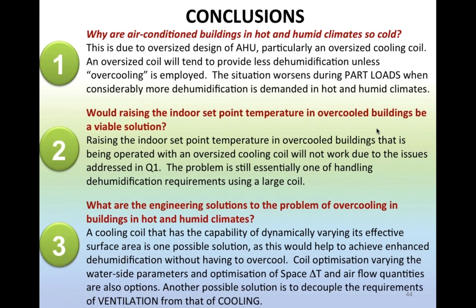It's very difficult. I am talking about a conventional vapor compression-based system. If you're going to achieve your latent load through some other means, like a desiccant system, it's a different computation. I didn't do that. I'm just taking the case that you've got chilled water supply temperature coming at 6 degrees. I think I used 6 degrees in my simulation, and I'm trying to ensure that we stay on that red line, the load ratio line, because that's the nature of the cooling loads in the space. I'm not changing the space temperature, mind you, I'm changing the supply air temperature. So to get to that right humidity level, we will still probably have to use the overcooling and reheating concept.